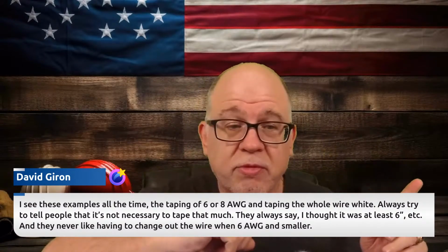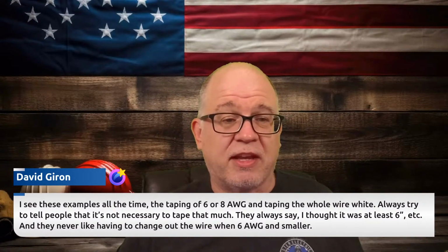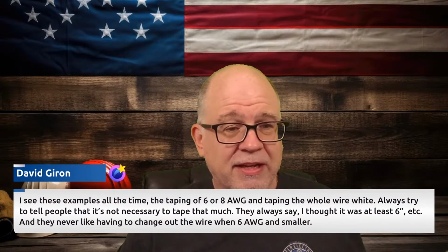Now, when it comes to the white, where I see it the most is the guys that install things like hot tubs and whatnot, and they have the 6 or the 8 already on their truck, and they want it to be the grounded conductor, and they end up wrapping it, and the inspector comes up and says, no, that's not going to work. And they're like, dude, it's copper. Copper's copper, right? I mean, that's what they say. Copper's copper. What does it matter, Paul? You're being a nitwit with it. Well, at the end of the day, code is code. And the real thing that I tell electricians, and I hate to say this, is the reason you do a lot of this stuff in the code, okay, you ready for this?